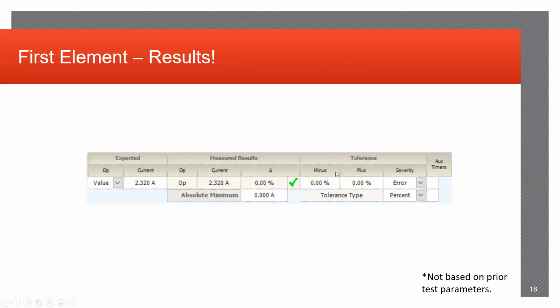And then as shown here, you can see that the results were actually perfect. Your expected result was supposed to be 2.32 amps. The relay picked up the contact at 2.32 amps when running the tests. And in fact, there was not even a tolerance that was needed, which is always nice.